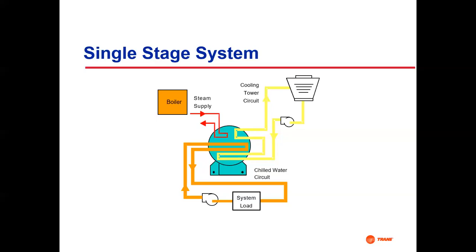This is the air conditioning load on the system. We took our 42 degree chill water and pumped it out all over campus. It got sucked up into air handlers, blown through cooling coils, picked up heat in the building, and got returned, typically at a 10 to 12 degree Fahrenheit increase. It goes back into the evaporator here, evaporating that water vapor sprayed on the outside of those pipes. 40 degrees inside this chamber, we got 42 degree water, and around and around and around she goes.